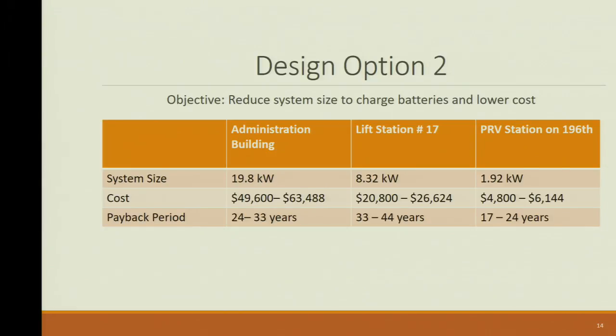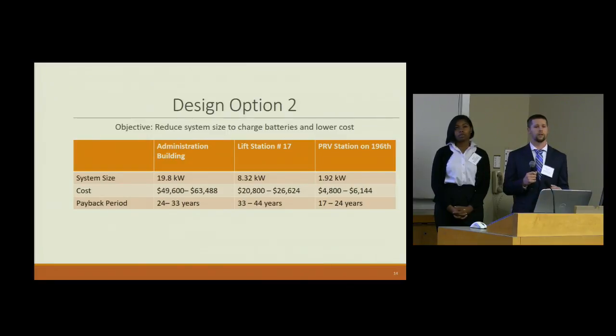For design option 2, our goal was to reduce the system size to reduce the total cost. We knew we had 72 hours worth of backup battery, so we designed the solar systems to charge those 3 days worth of batteries in 1 day. Using the administration building as an example, the system goes down to a 19.8 kilowatt system. The price gets reduced to $49,000 on the low end to $63,000 on the high end, and the payback period is 24 to 33 years.